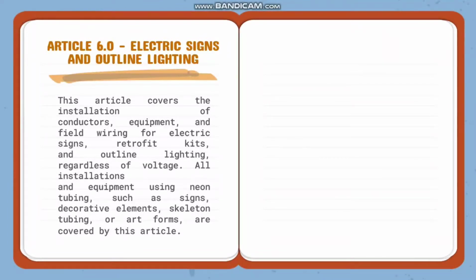So as per Chapter 1, electric sign is defined as any fixed, stationary, or portable self-contained electrically illuminated utilization equipment with words or symbols designed to convey information or attract attention. Whereas yung outline lighting is an arrangement of incandescent lamps or electric discharge lighting or other electrically powered light sources to outline or call attention to certain features such as the shape of the building or the decoration of a window. So these systems can include many lamp types such as LED, HID, and fluorescent.